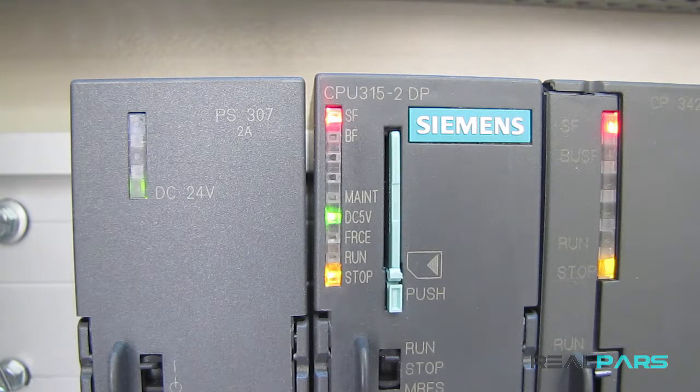The next light that's on here is the bus fault indicator LED light. This red light also turns on to let us know that there is an error in the network we have. For instance, if we have used a Profibus DP network, it could be that one of the connectors didn't connect correctly. Or perhaps there's a disconnection in the cables in the network. Or it could be that there's been an overlap between the addresses of the facilities in our network. For example, if we have chosen 2 for the CPU address in the network configuration, and then mistakenly we choose 2 for another module address, like a CP module, this causes an address overlap, and hence the bus fault light will come on.